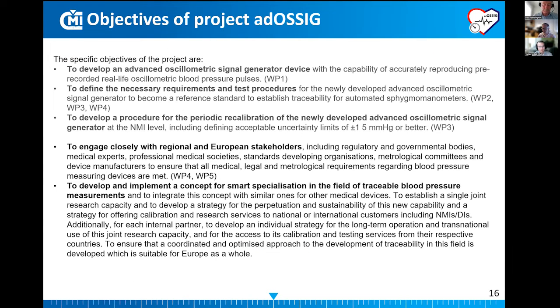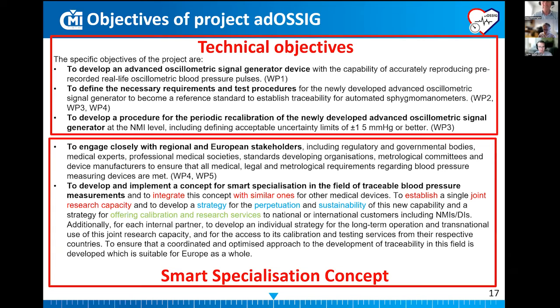With this in mind, the objectives of our project were drafted, and we have 5 of them. They can be divided into 2 groups. The first one being technical objectives, which revolve around developing a new standard. We call it the Advanced Oscillometric Signal Generator, which is a device that accurately reproduces real-life oscillometric signals that are then used in testing of the devices. And because this is a more or less new device, we also need testing procedures for this device, and to provide traceability, an uninterrupted calibration chain for our new standard.